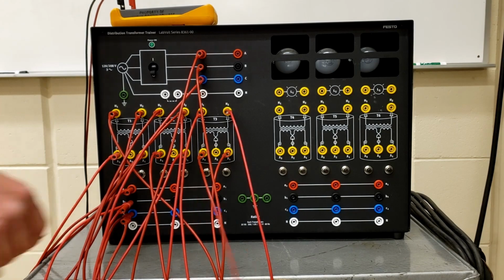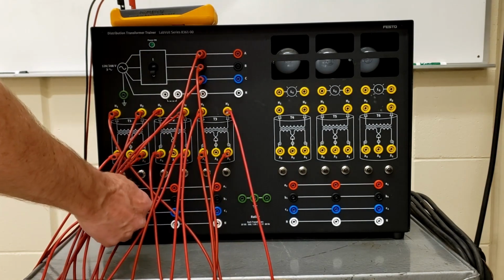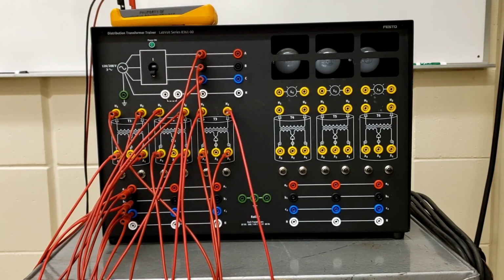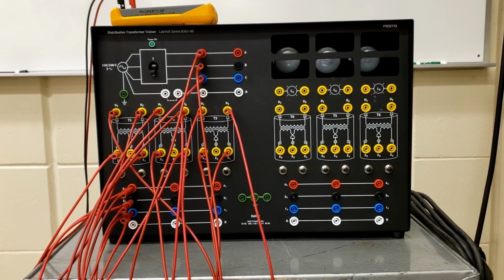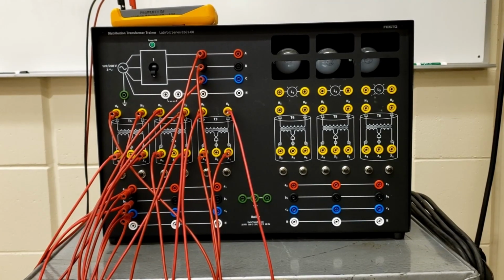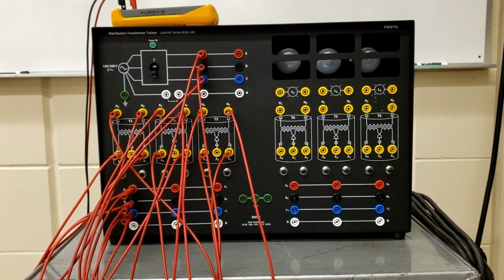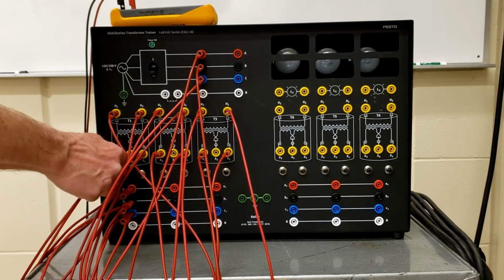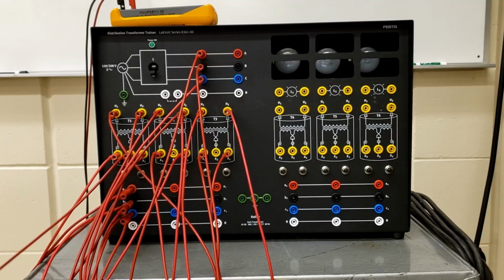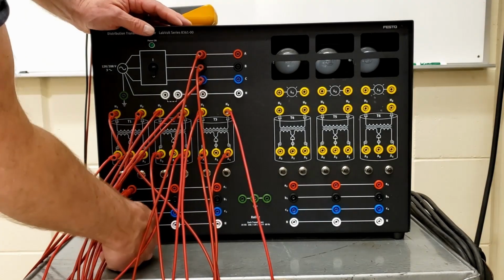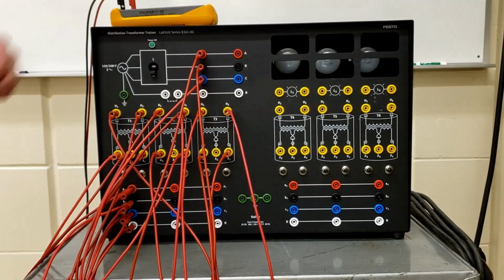Is it? Yes. Okay, and now this is identical to what we were doing before, but we are bonding part of this. So the X2 is now going to the neutral, and the neutral is being bonded to ground. So X2 of the first transformer here is going to the neutral, so it's going to feed our neutral bus. And then our neutral bus is then going to be bonded to ground.